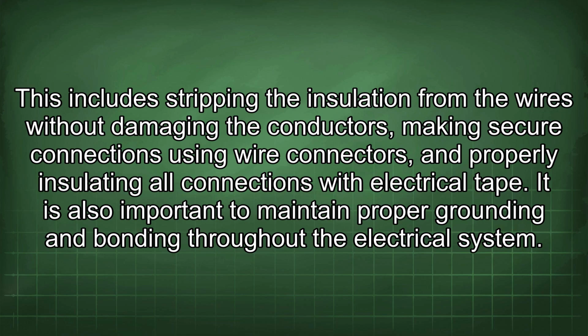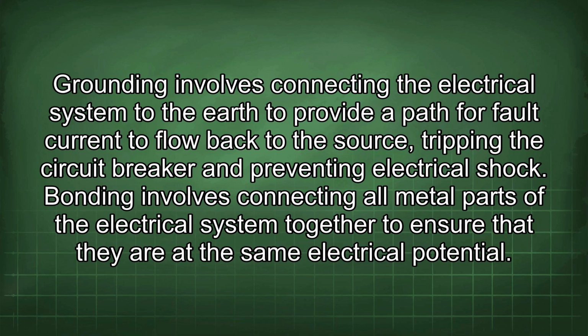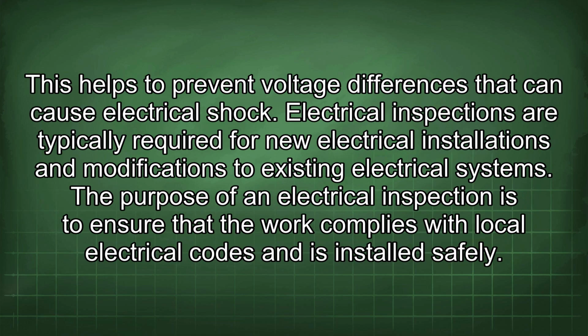It is also important to maintain proper grounding and bonding throughout the electrical system. Grounding involves connecting the electrical system to the earth to provide a path for fault current to flow back to the source, tripping the circuit breaker and preventing electrical shock. Bonding involves connecting all metal parts of the electrical system together to ensure that they are at the same electrical potential, which helps prevent voltage differences that can cause electrical shock.